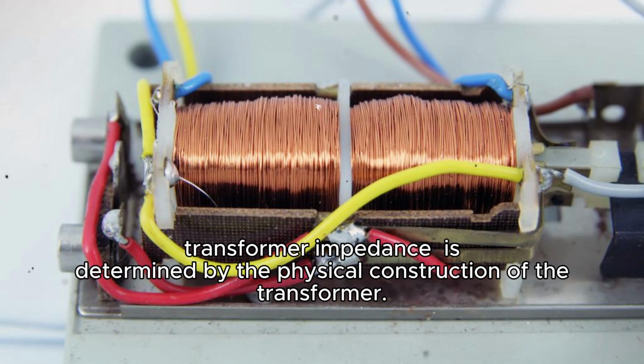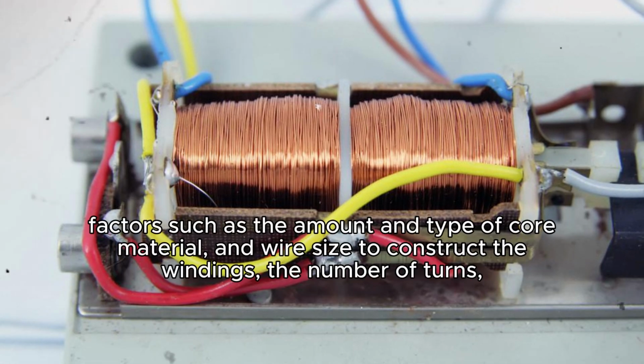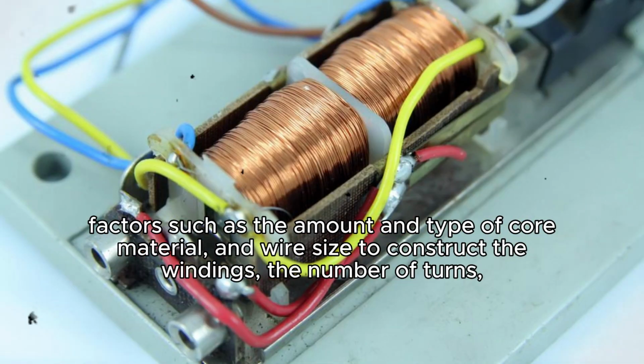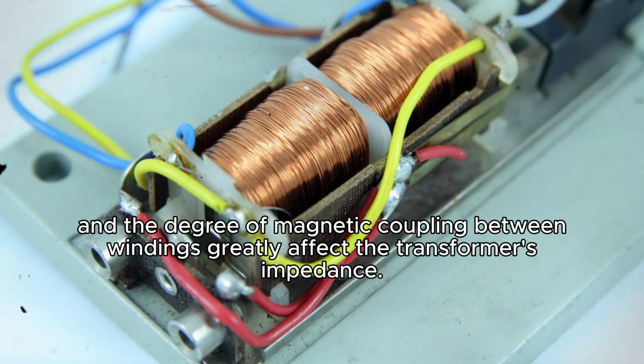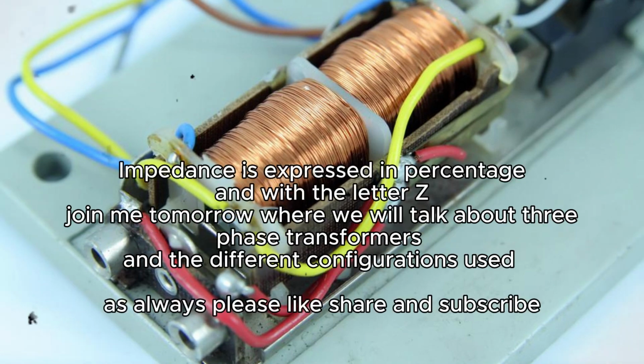Transformer impedance is determined by the physical construction of the transformer. Factors such as the amount and type of core material, the wire size used to construct the windings, the number of turns, and the degree of magnetic coupling between windings greatly affect the transformer's impedance. Impedance is expressed in percentage and with the letter Z.